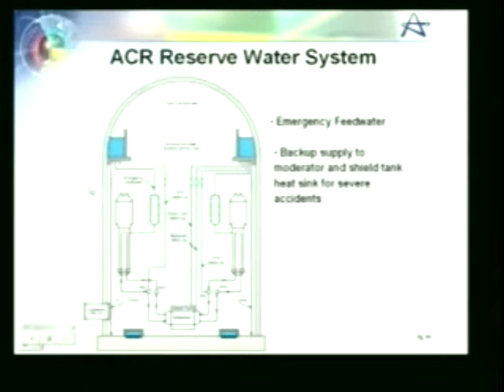Our ACR reserve water system is a passive system. We have a tank of water, sort of like a donut, at the top of the reactor building that is gravity driven. It provides a feed to the steam generators in case of a total loss of the main feedwater system, and also serves as a backup to our long-term cooling system, and as a backup to the moderator and shield tank in case of severe accidents.